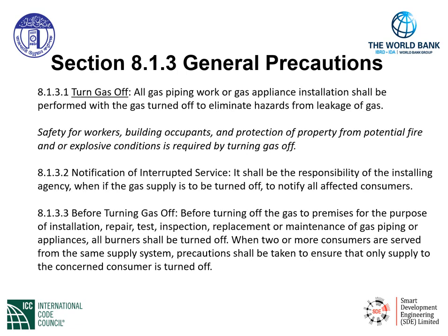So if we look at this completely, we must understand that if you are working on the gas system where two or more consumers are served, then we need to make sure that only the customer requiring the service, if the gas must be turned off, is turned off, not affecting any of the other customers tied to that particular gas piping system.